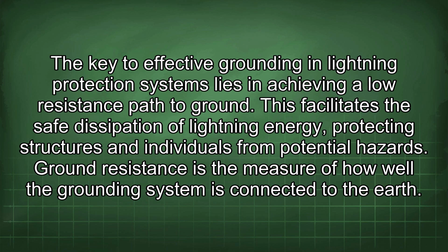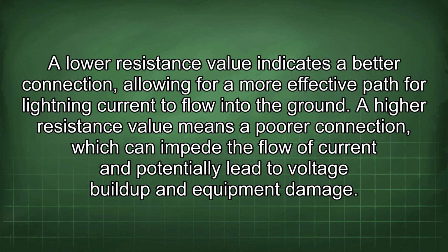This facilitates the safe dissipation of lightning energy, protecting structures and individuals from potential hazards. Ground resistance is the measure of how well the grounding system is connected to the earth. A low resistance value indicates a better connection, allowing for a more effective path for lightning current to flow into the ground. A higher resistance value means a poor connection, which can impede the flow of current and potentially lead to voltage buildup and equipment damage.